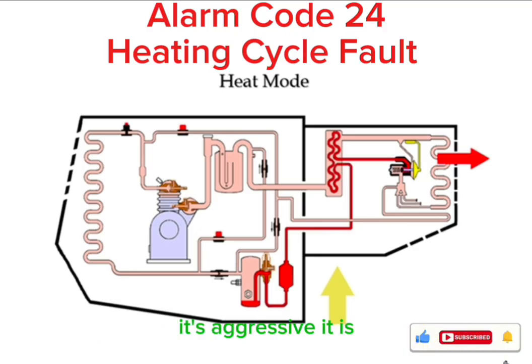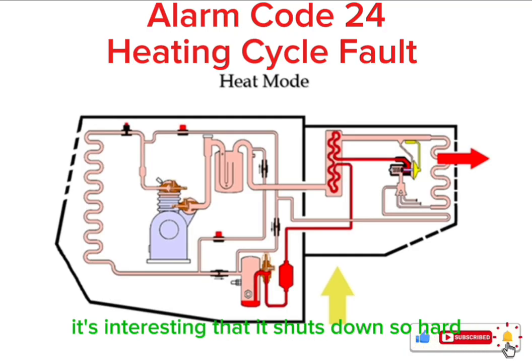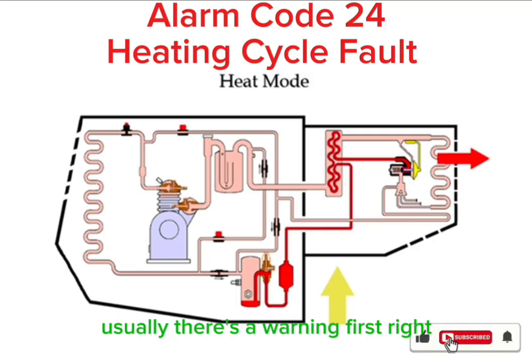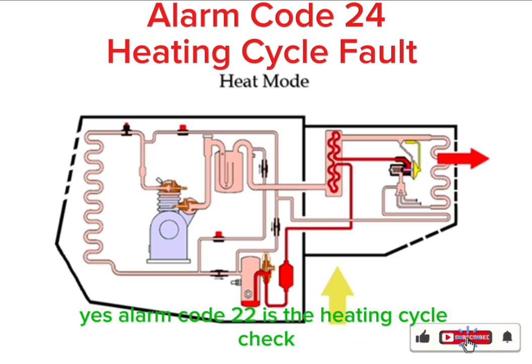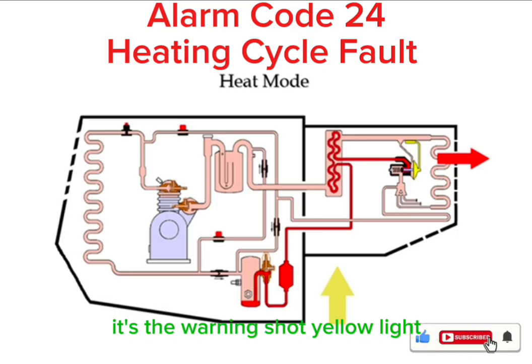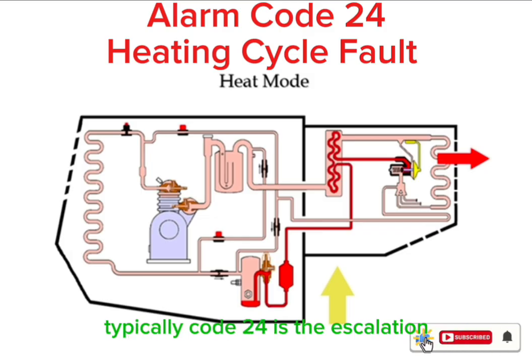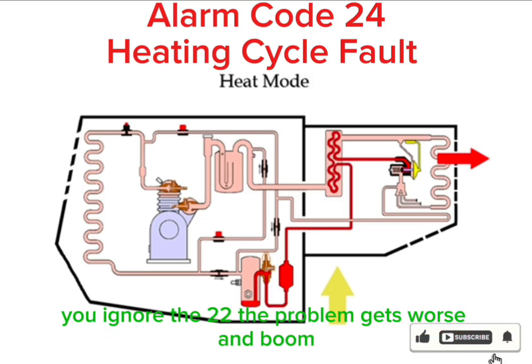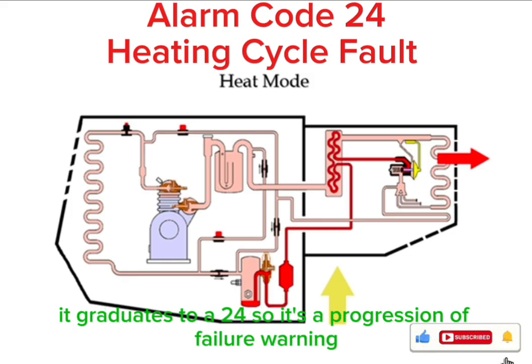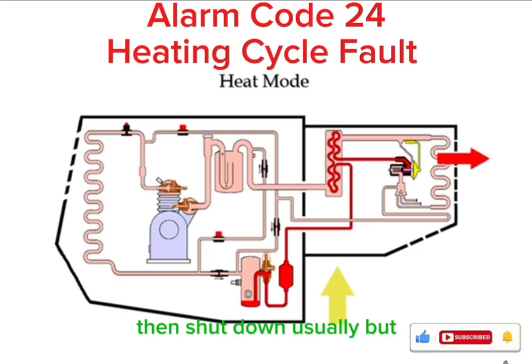It's aggressive. It is. It's interesting that it shuts down so hard. Usually there's a warning first, right? I'm thinking of alarm code 22. You're on the right track. In a perfect world, yes. Alarm code 22 is the heating cycle check. It's the warning shot. The yellow light. It's the unit saying, hey, I'm having a little trouble here. You might want to look at this. Typically, code 24 is the escalation. You ignore the 22, the problem gets worse, and boom, it graduates to a 24. So it's a progression of failure. Warning, then shut down. Usually.